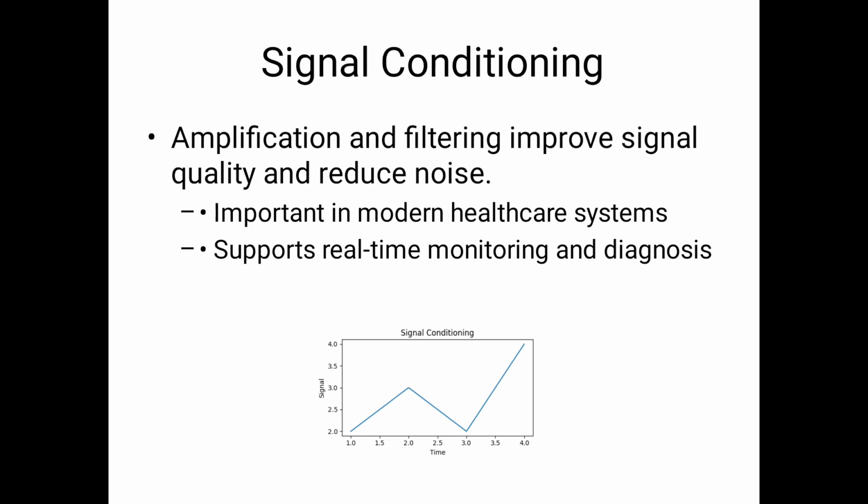Next is the signal conditioning. Once the raw electrical signal leaves the sensor, it must pass through the signal conditioning stage, because it will mostly be weak and heavily affected by environmental noise. This stage utilizes precision instrumentation amplifiers to boost the signal amplitudes, along with bandpass filters for removing movement artifacts and power line interference. Purifying the signal increases the data quality and ensures a clean, accurate representation.